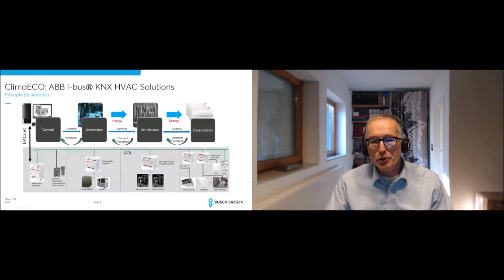This we are doing in the room, of course, but to supply the right water into the rooms, we need a distribution part, meaning a heating cooling circuit controller, a mixing valve to supply the right temperature to this unit. A unit can be a collection of rooms, maybe an apartment, and this mixing valve has the task to supply the right water regarding temperature, but also the right amount of water. So we also control the pump, and we measure the flow and return flow temperature to control it in the right way. And this can be done by the heating cooling circuit controller, which is a KNX device.